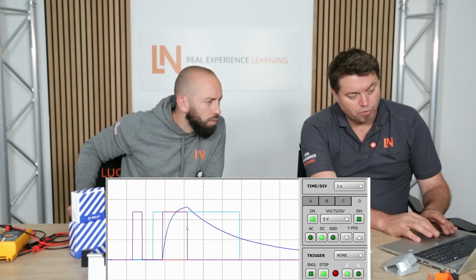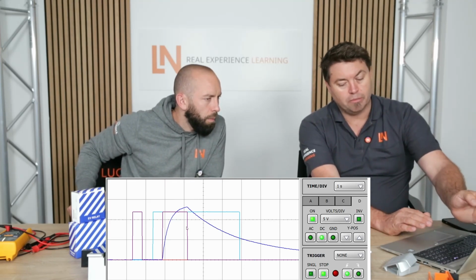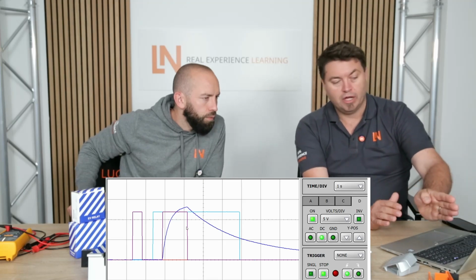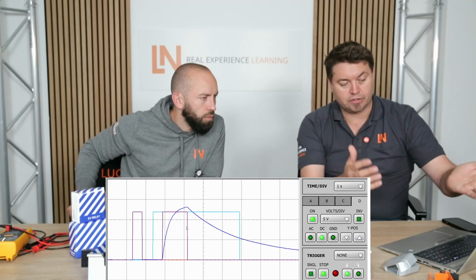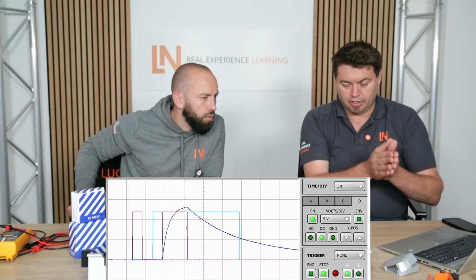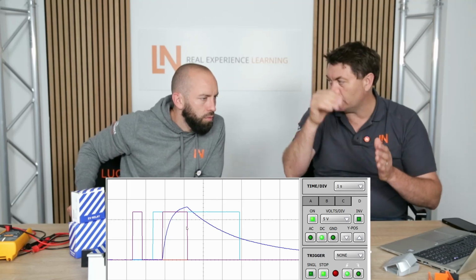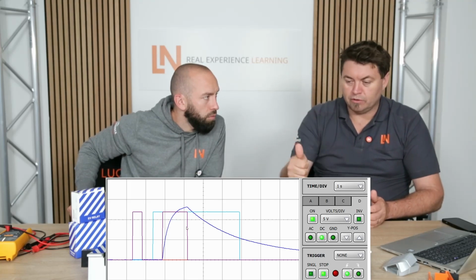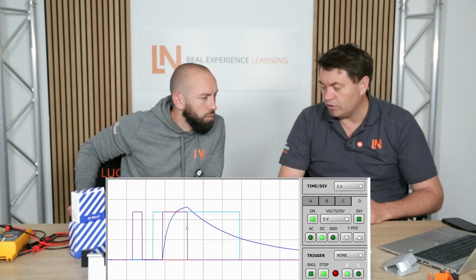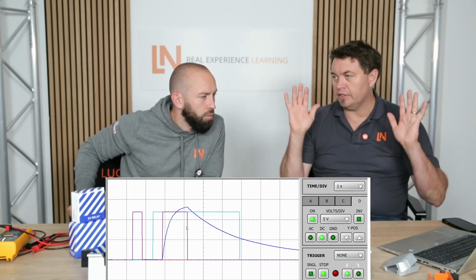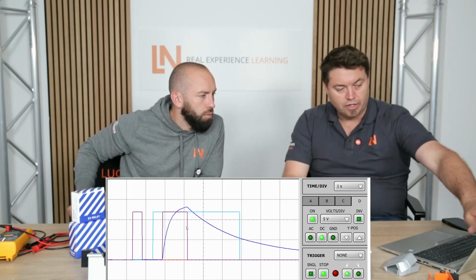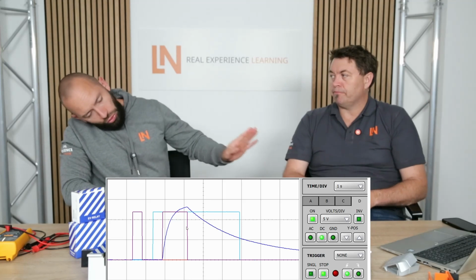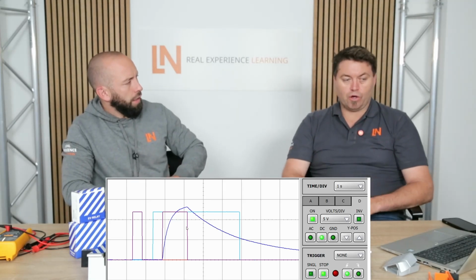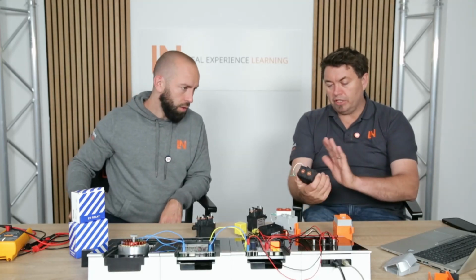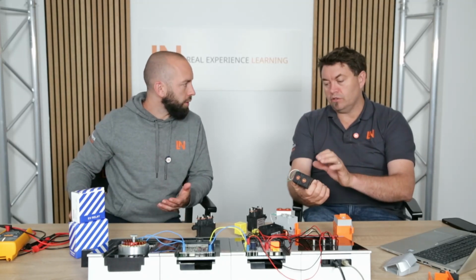What we saw before was that the main positive relay would get switched on and you'd get full voltage. But right here, it's done the pre-charge correctly, done the negative side correctly, we've filled up the capacitors, and then the BMS says okay, switch the main positive relay on, and nothing. Then it's like, okay, something's wrong, switch the system off, goes into passive discharge. But this has nothing to do with welded shut contacts. It's just a broken wire problem, or it could be the control side of the relay, or the contacts of the relay itself, or the coil being broken.